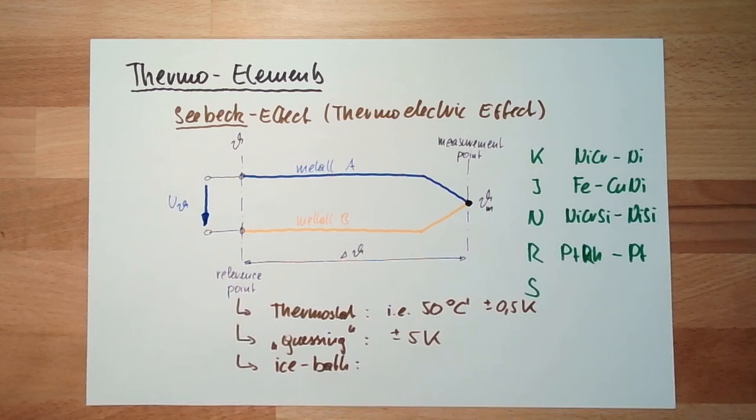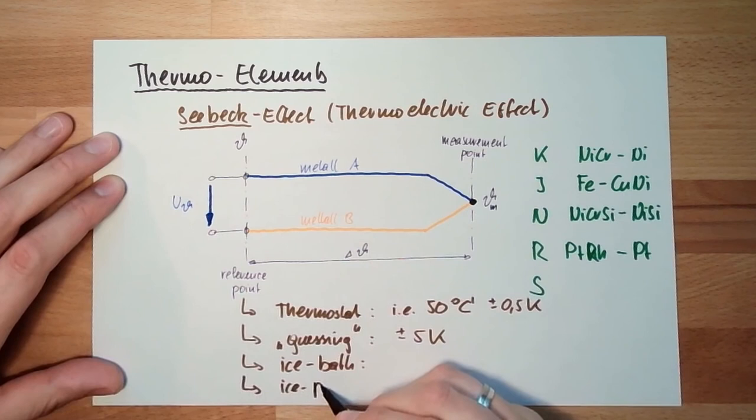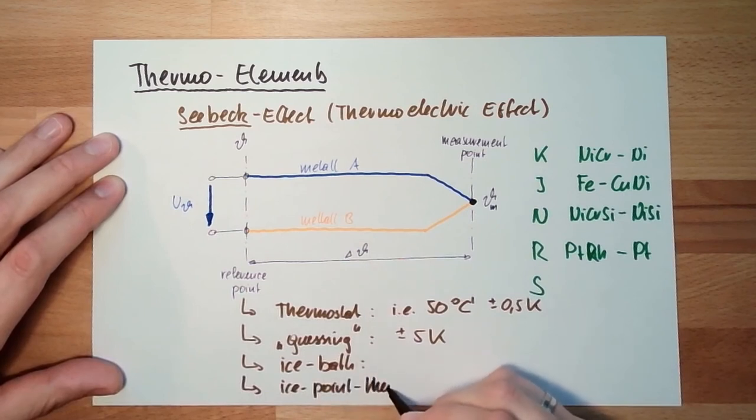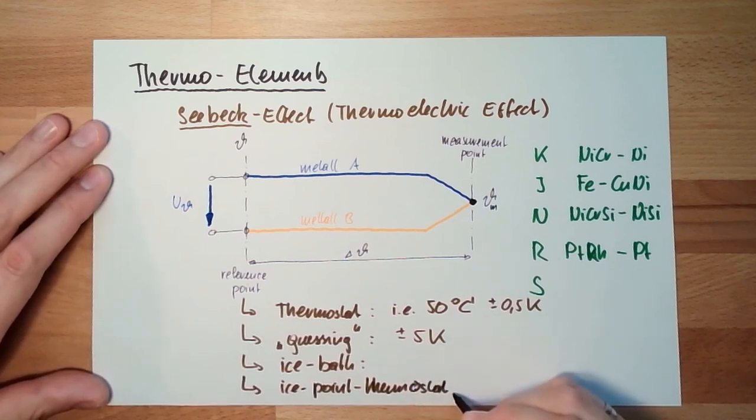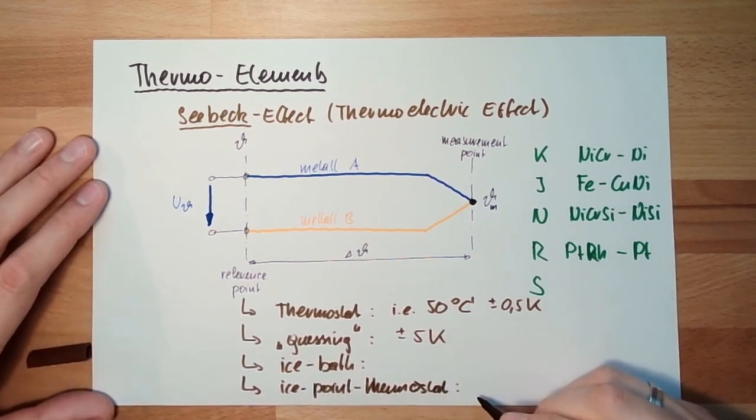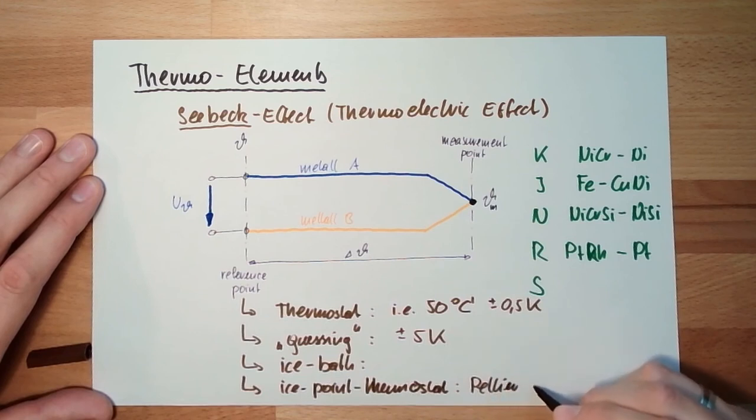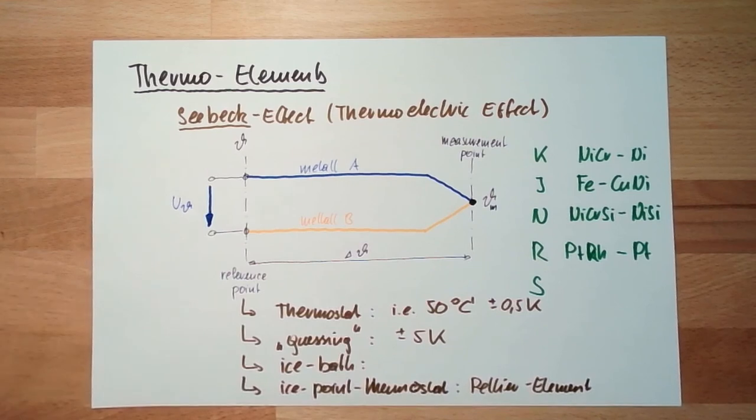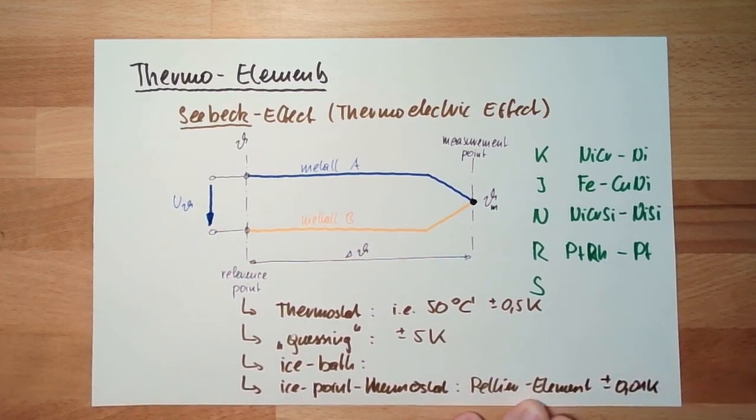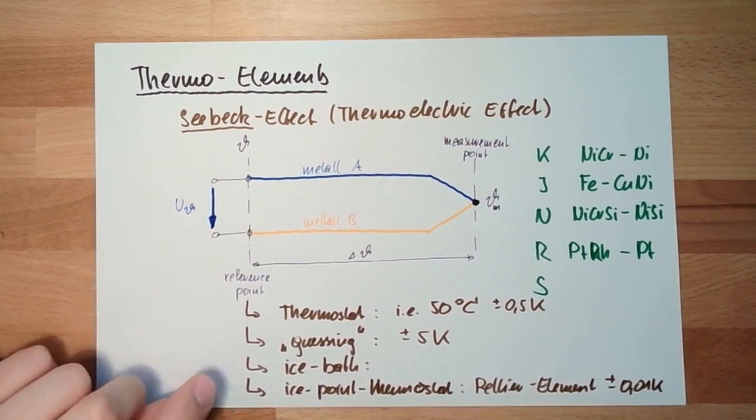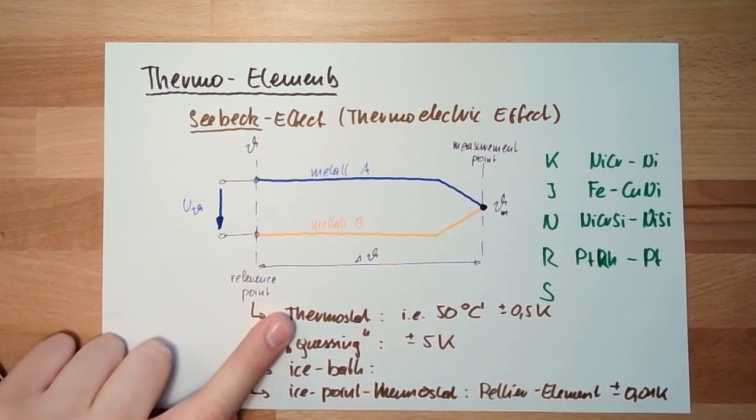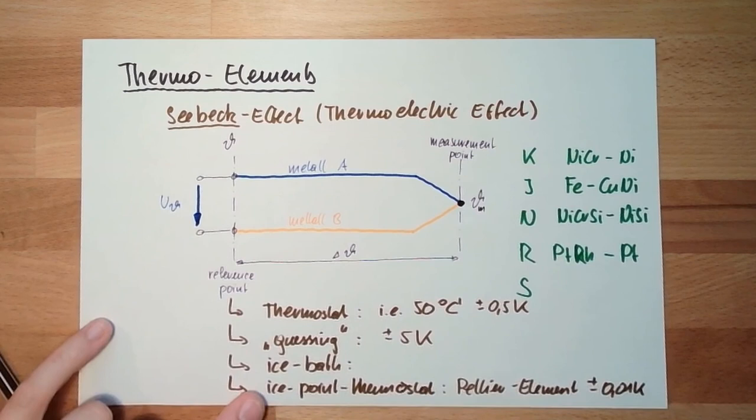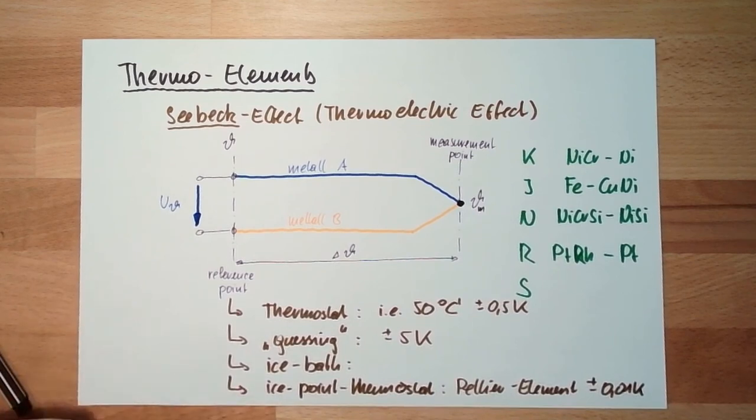However, there's also the so-called ice-point thermostat. These ice-point thermostats are produced usually with some Peltier element. They are very accurate. They really maintain zero degrees Celsius with the accuracy of plus minus 0.01 Kelvin. They recognize ice melting and so on. These are very accurate. This is often done, and if you need to be more accurate, use this. If you don't have the possibility and it's just a temporary measurement, use the ice bath.